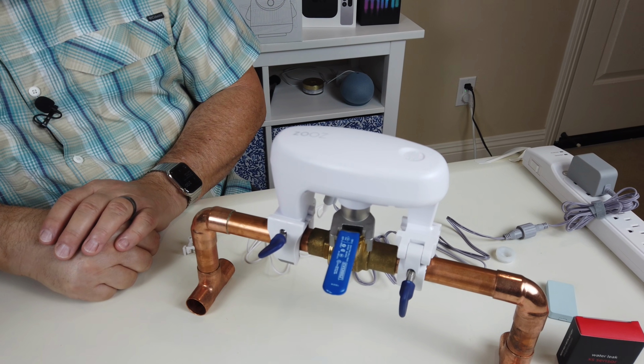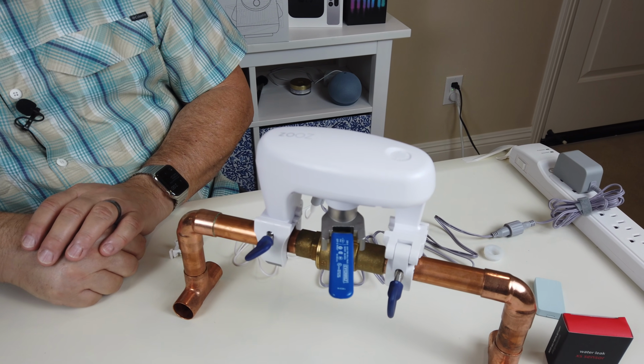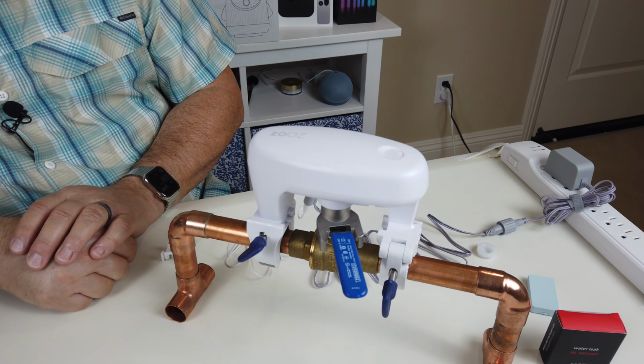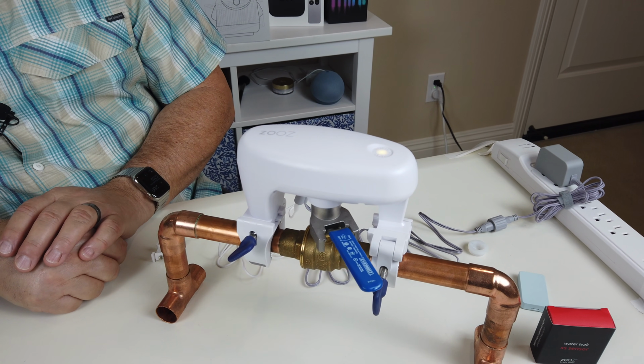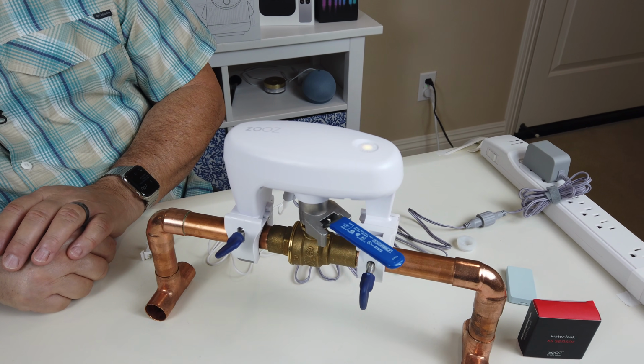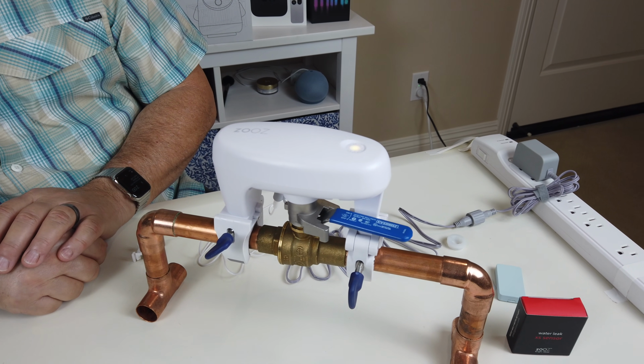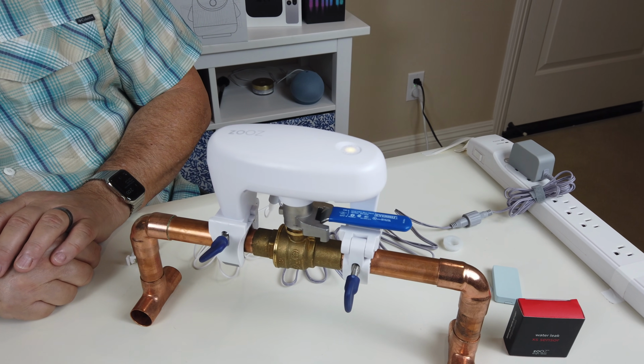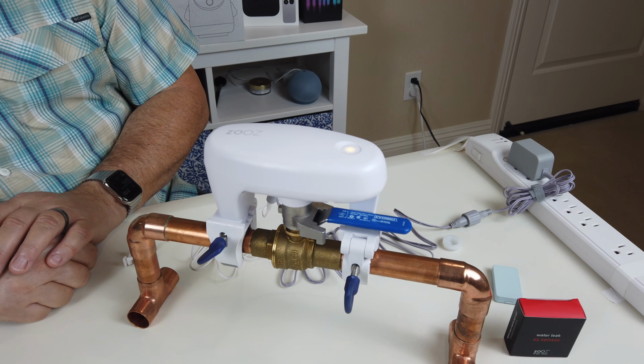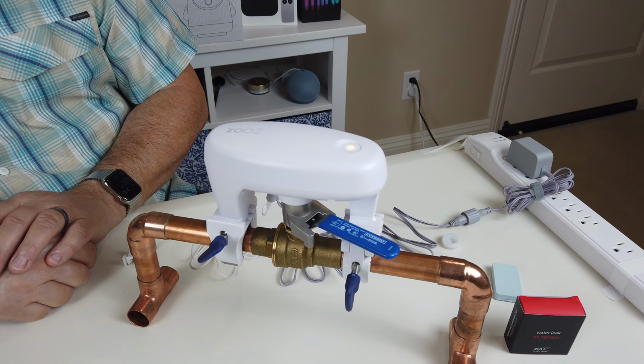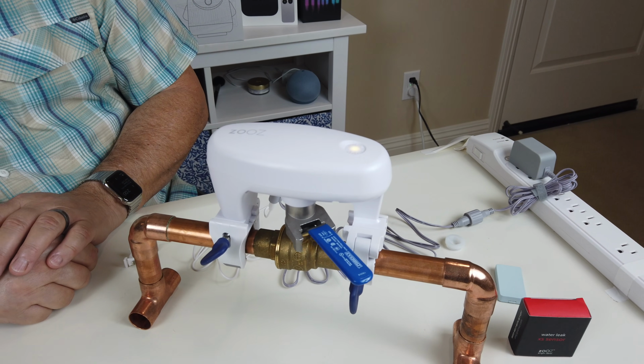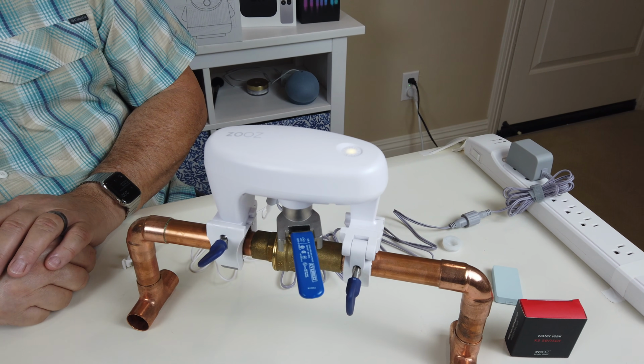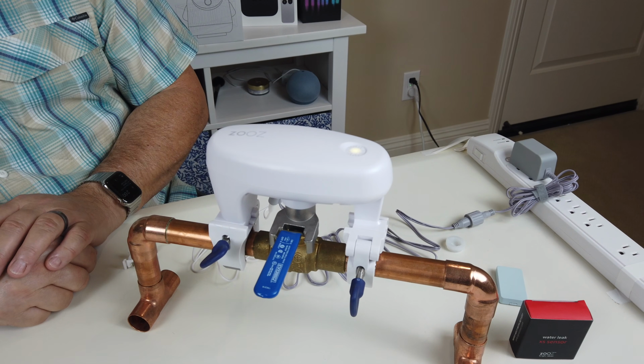Now what it's doing is calibrating. It's going to go from the closed position where it's at right now to the open position. You can see it takes a little while, but it's trying to sense where the valve's open and closed positions are, because you don't want it to over-rotate. When it's done, it'll leave it in the closed position.